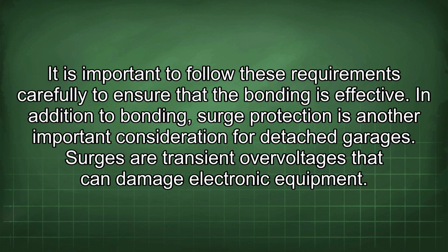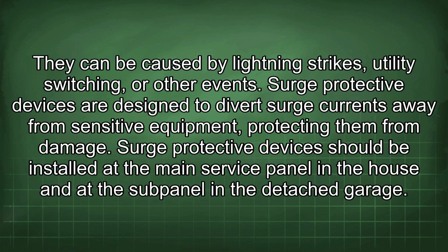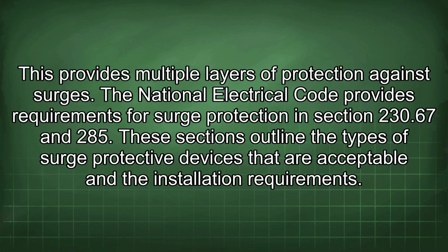In addition to bonding, surge protection is another important consideration for detached garages. Surges are transient overvoltages that can damage electronic equipment. They can be caused by lightning strikes, utility switching, or other events. Surge protective devices are designed to divert surge currents away from sensitive equipment, protecting them from damage. Surge protective devices should be installed at the main service panel in the house and at the sub-panel in the detached garage. This provides multiple layers of protection against surges. The National Electrical Code provides requirements for surge protection in Section 230.67 and 285. These sections outline the types of surge protective devices that are acceptable and the installation requirements.